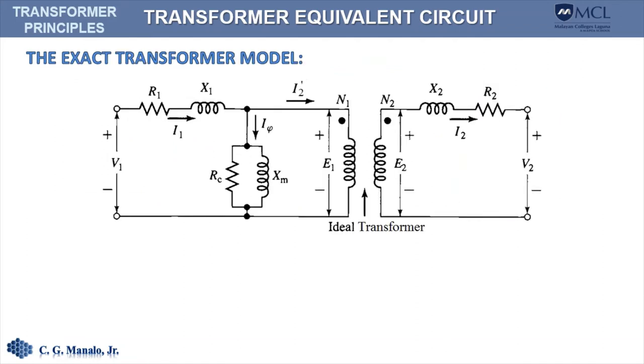Here is the complete model of the transformer, which is also called the exact transformer model. We have combined the effects of the core loss and the magnetizing current into a single shunt circuit. That circuit will draw a current I sub phi, which is actually the exciting current. Now because of the presence of the core loss and magnetizing current model, the current here is not anymore I sub 1, but a different current. So we relabeled this with a current I sub 2 prime.